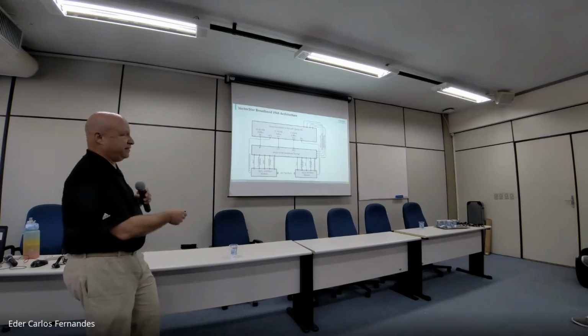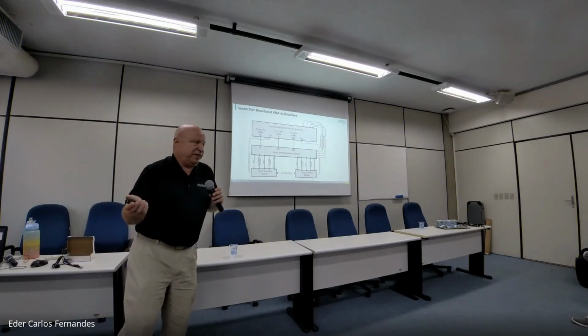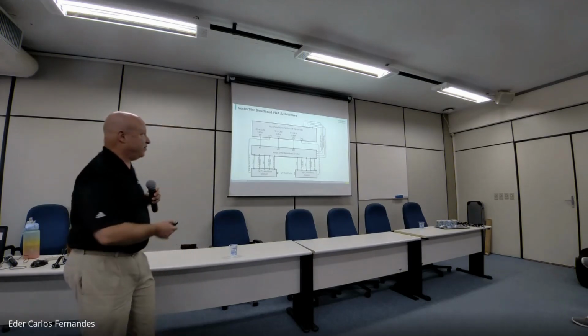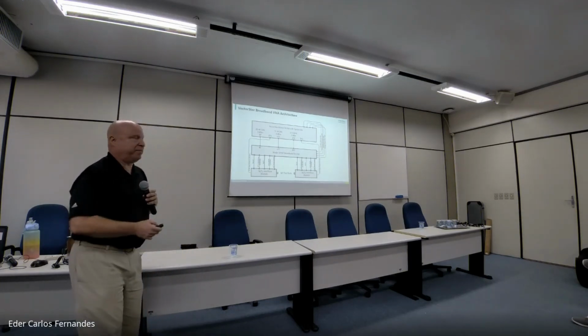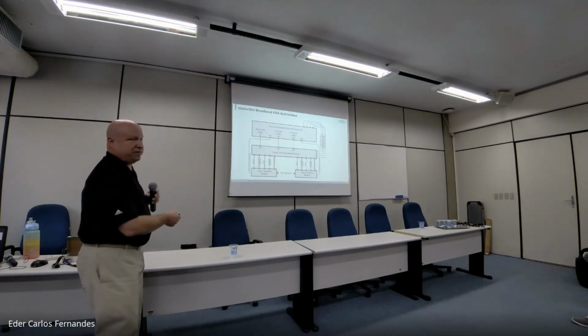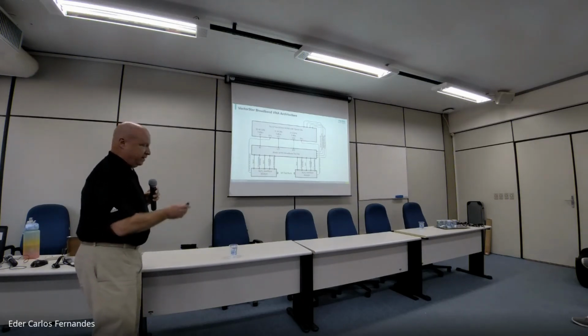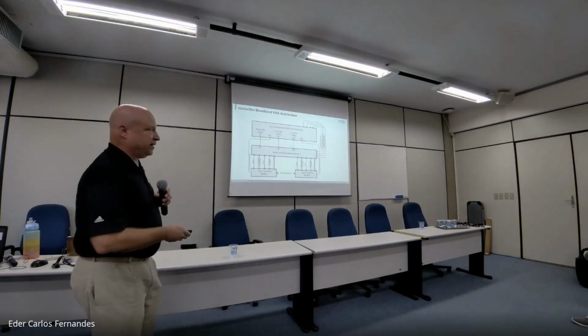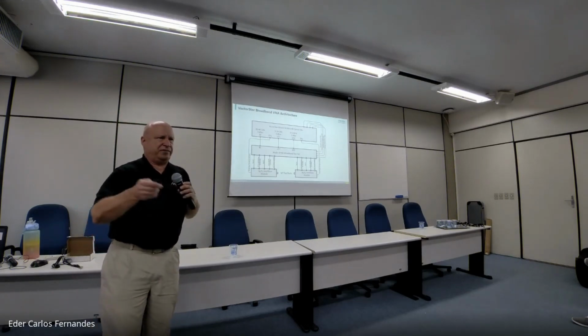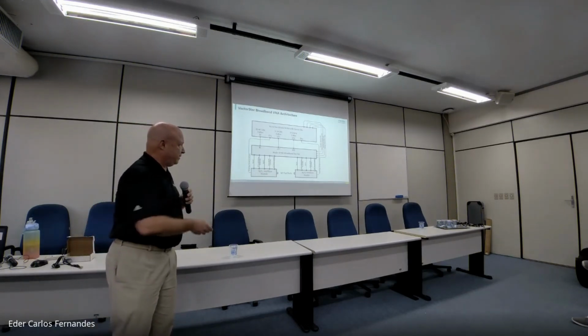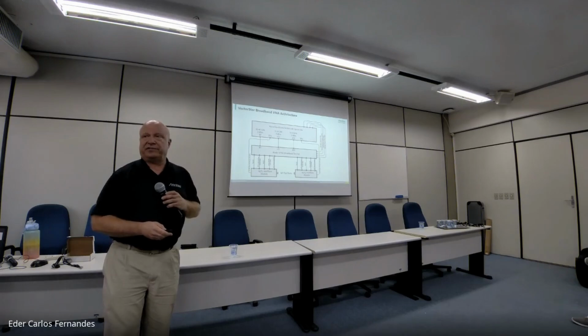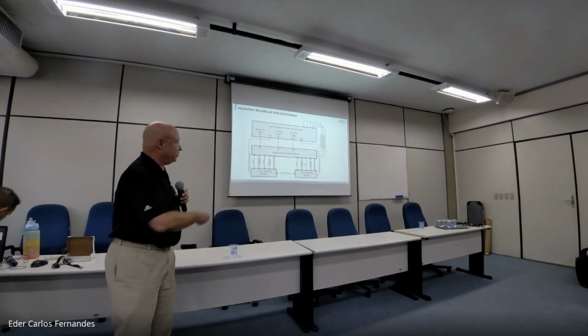And they bypass the mainframe receiver because you don't need it. You're going straight in at IF, get digitized right away. So the IFs don't take the same path as the lower frequency or the microwave signals do, going through the receiver and the VNA. So there's just a basic interconnect. That's where all the cables are between the test set and the mainframe and the modules that you see in the system. That's what they do.